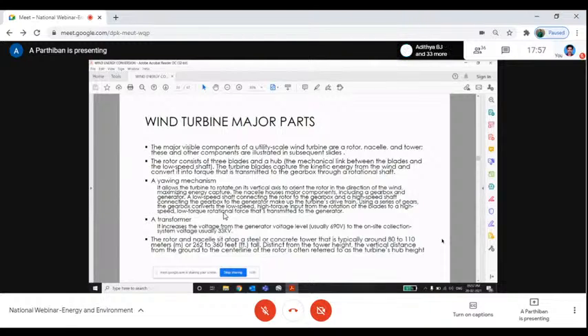But in the new era, we have the transformer in the top of the nacelle itself. The nacelle is placed at around 300 feet height, and in the same nacelle the transformer is there. It is a dry type transformer, which is kept in the top of the nacelle.